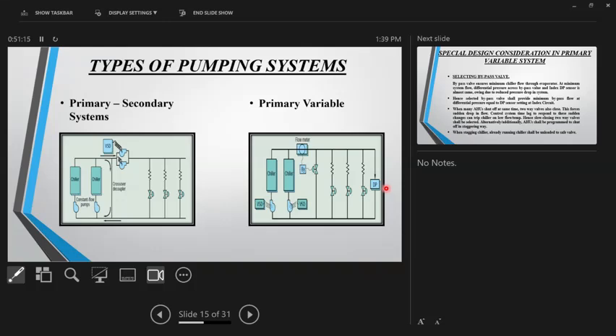Hello, sir. This theory is understood, but this will be only applicable when the bypass valve is placed before any load, am I correct? Yes, that's correct. Would this theory still be applicable if the bypass is connected towards the end of the load? Yeah, if this was here, somewhere here, the same theory applies. The pressure drop in this is zero, the same thing. So this is a universal kind of theory, irrespective of whether this is here or here or here. The theory is that the pressure drop in this at very, very low flow is almost zero. So it holds good for both the situations. Got it, sir. Thank you.